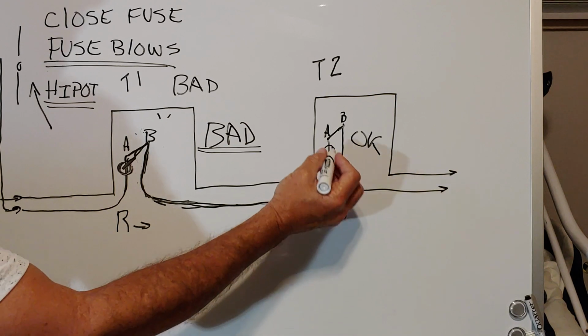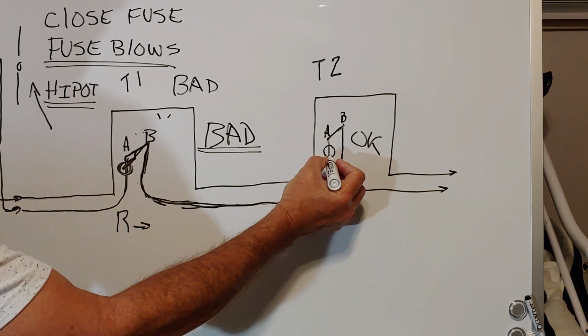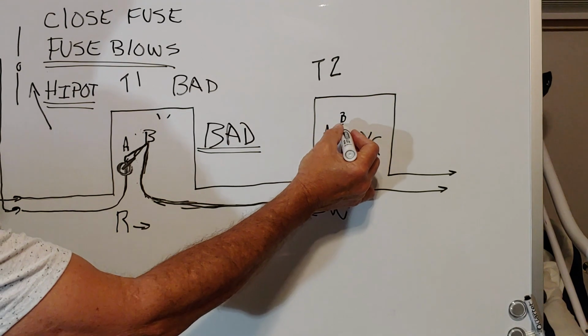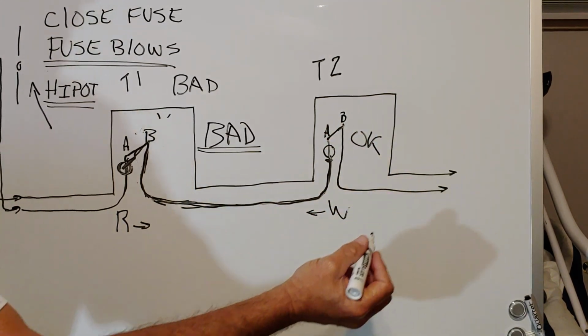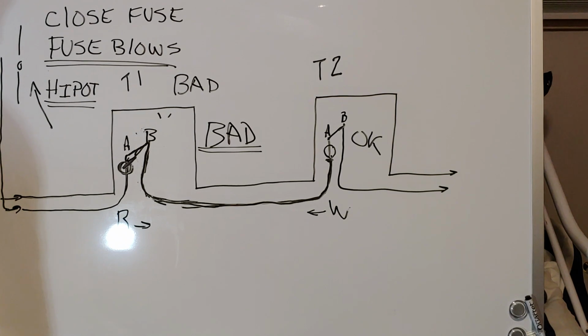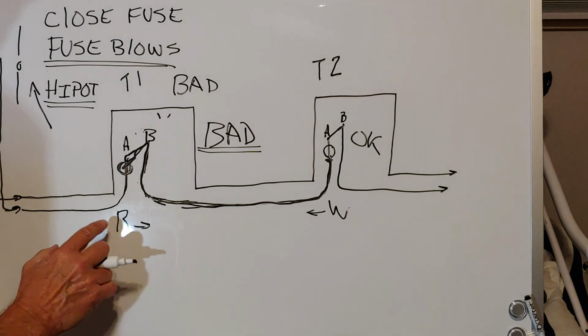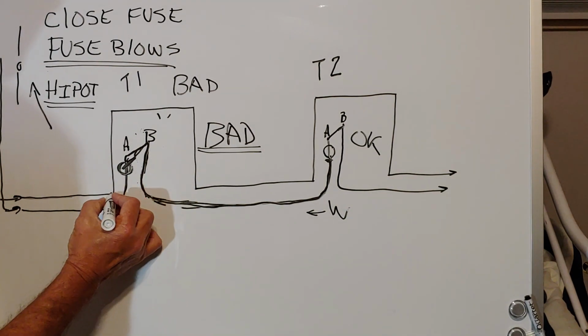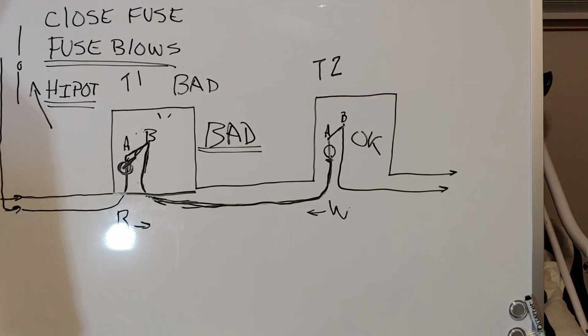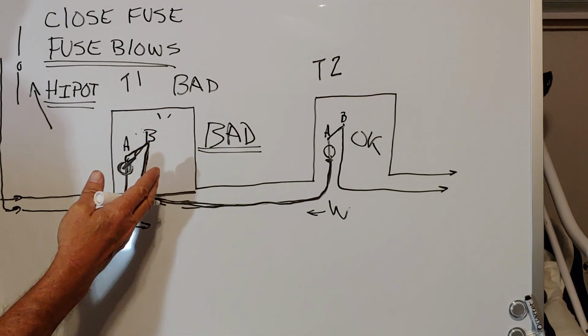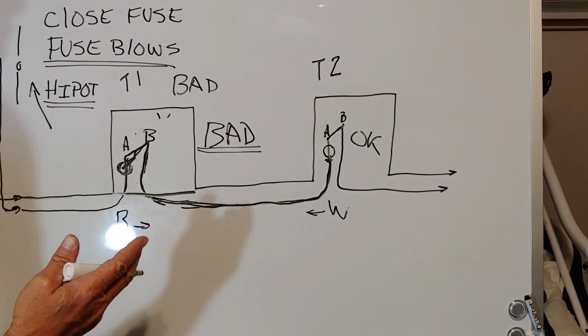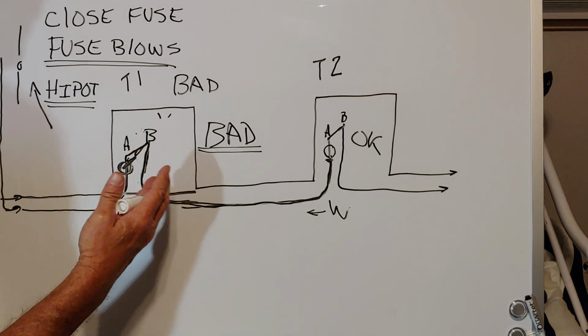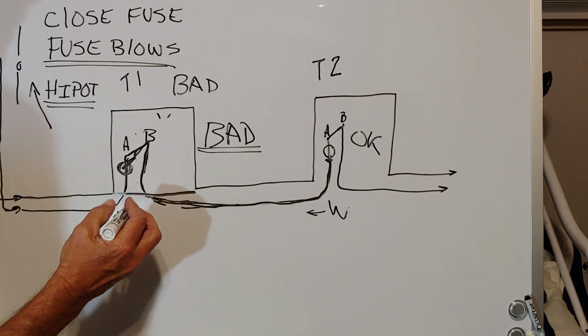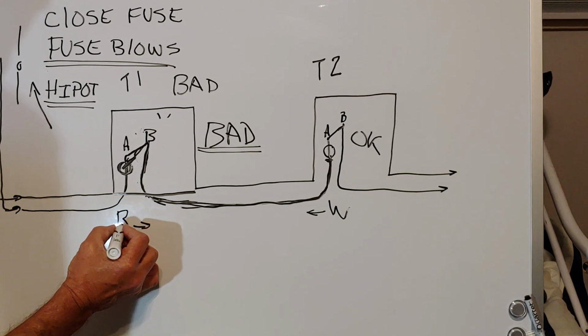Now the next one down the line, you've got it mounted on the A phase. What's it doing? It's watching this cable inside the transformer all the way out and then stops, and on and on and on. Okay, that'll be it for this video. Just wanted to give you some information that included not only the cable, but the transformer, maybe the suspect fault condition also. If you run into something like this, usually if the transformer is bad, there's going to be some smoking, charring, maybe a little bit of oil leak coming out of it, but you will see some indication on the transformer. I just wanted to give you the instruction of what the fault indicator does see.